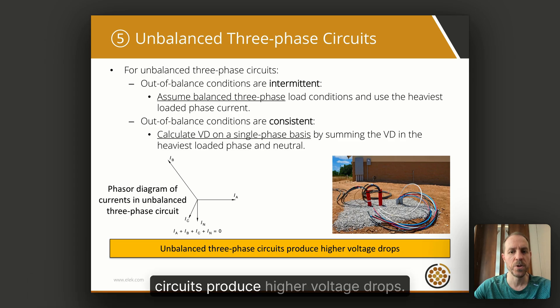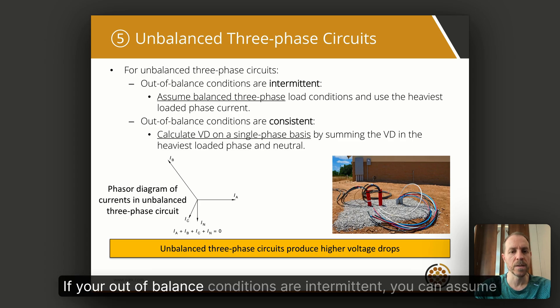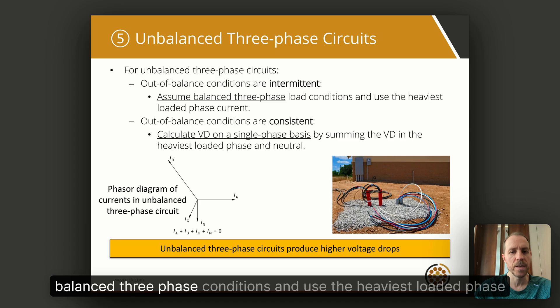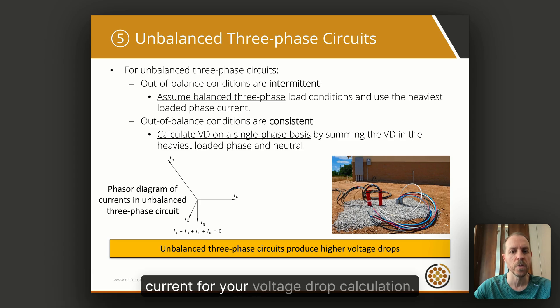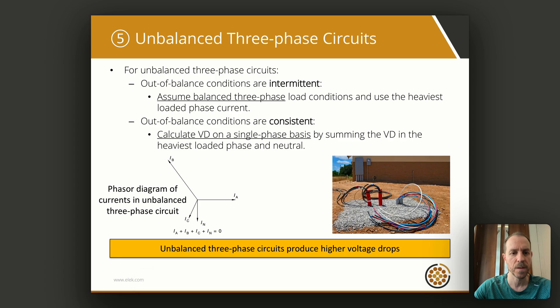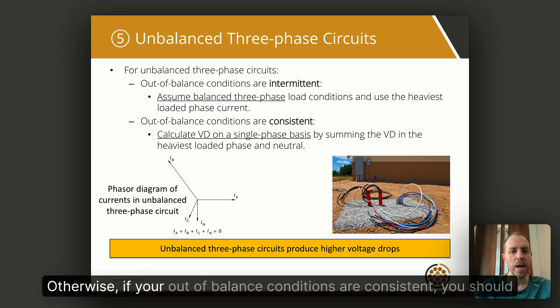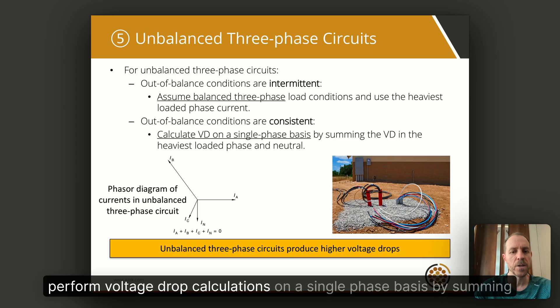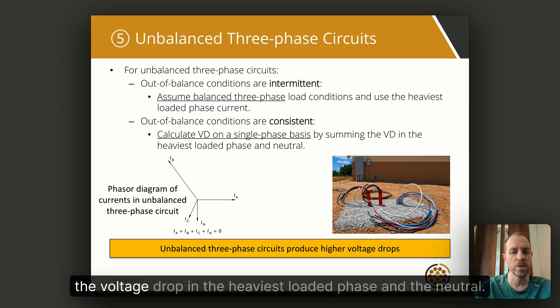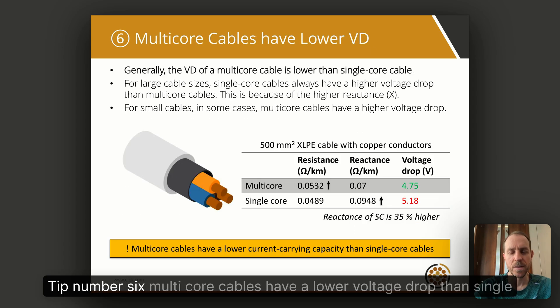Tip number five: unbalanced three-phase circuits. Unbalanced three-phase circuits produce higher voltage drops. If your out-of-balance conditions are intermittent, you can assume balanced three-phase conditions and use the heaviest loaded phase current for your voltage drop calculation. Otherwise, if your out-of-balance conditions are consistent, you should perform voltage drop calculations on a single-phase basis by summing the voltage drop in the heaviest loaded phase and the neutral.